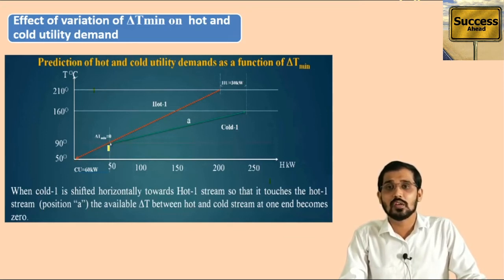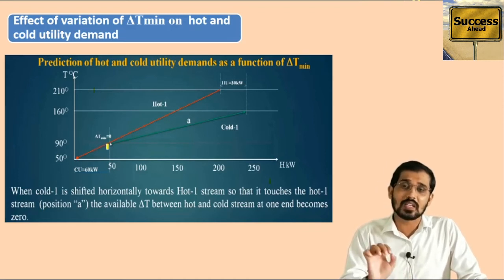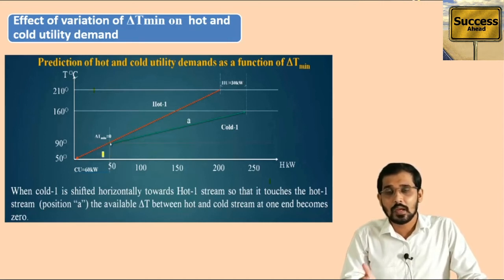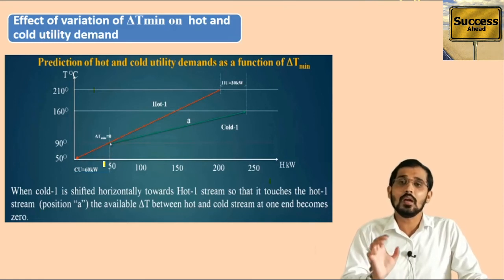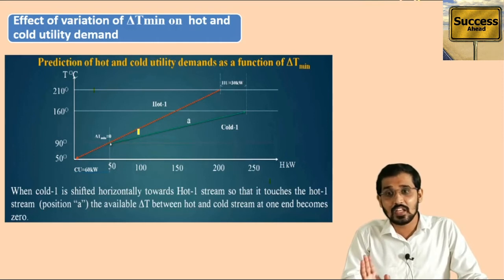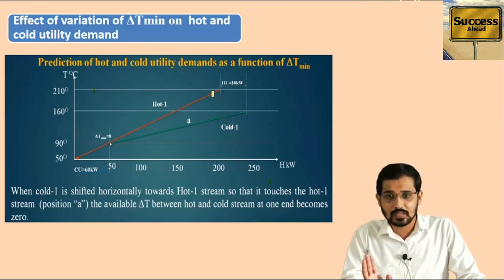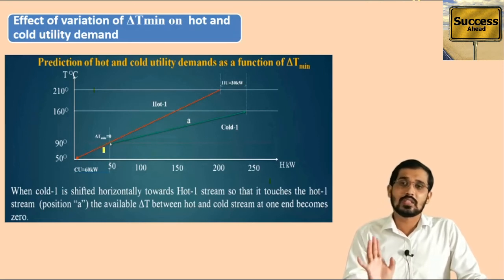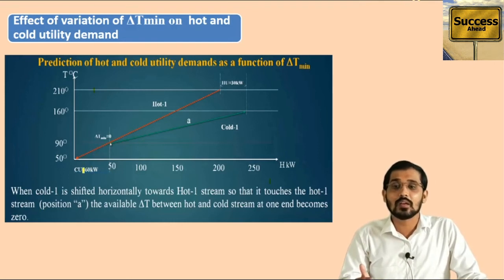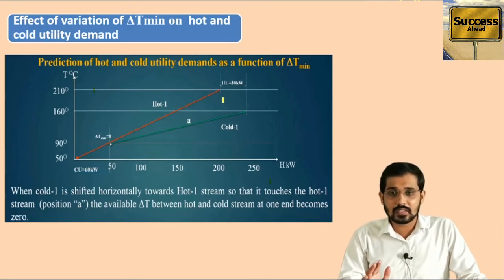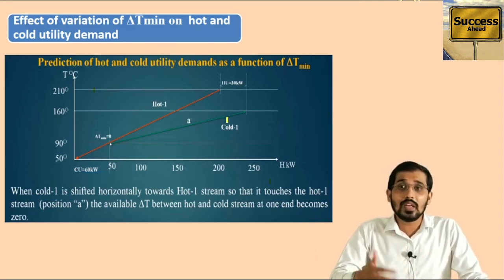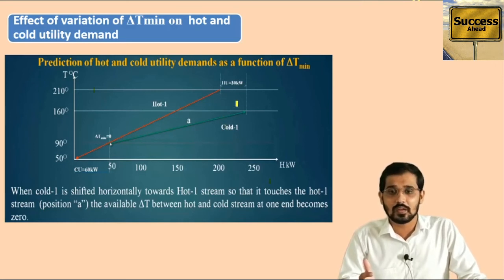This extra part of the hot stream in the bottom section requires extra cold utility to extract heat from it, because no cold stream is available in that section. We can exchange heat between cold and hot streams only in the overlapping area. Beyond that overlap, there is no cold stream available. So to remove excess heat from this extra part of the hot stream, extra cold utility is required — that is nothing but Cu, and its value is 60 kilowatts.